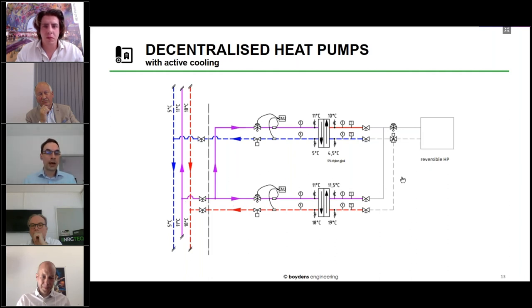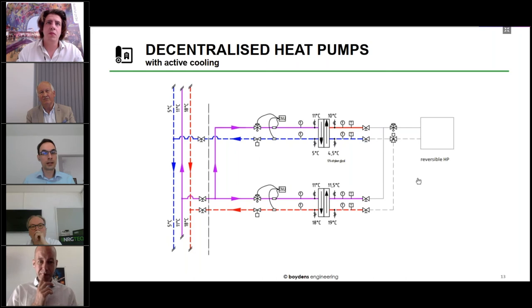Now, one may ask the question, why do we need a loop here with three pipes? Because we could also do a two-pipe loop, and that is also done on some projects. The main reason is that if we use a three-pipe system with a separate return piping, then we can really make sure that the return temperature is either as high as possible or as low as possible. When we want to inject that water back into the aquifer thermal energy system, we can make sure that we are injecting just cold or hot water. And the temperature difference between the hot and the cold water must be as high as possible, because then we get a lot of seasonal storage capacity in the aquifer thermal energy system.